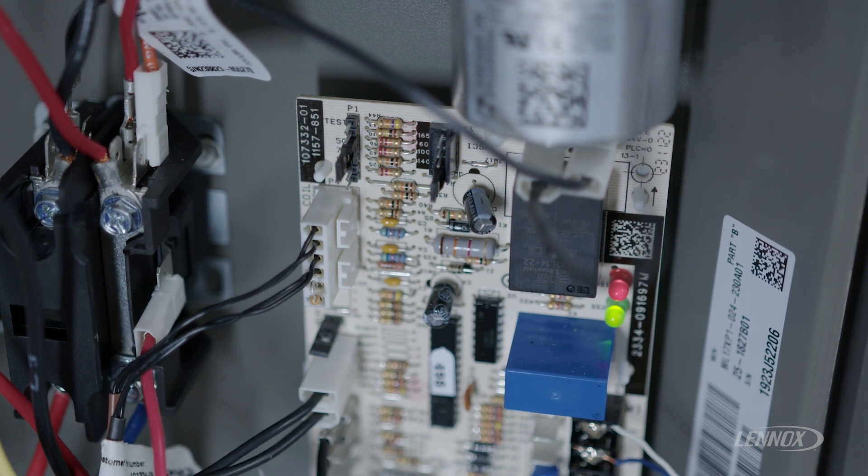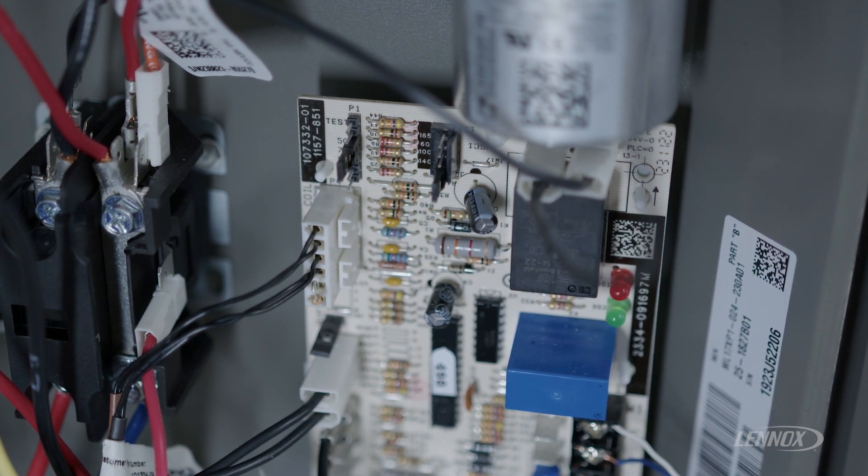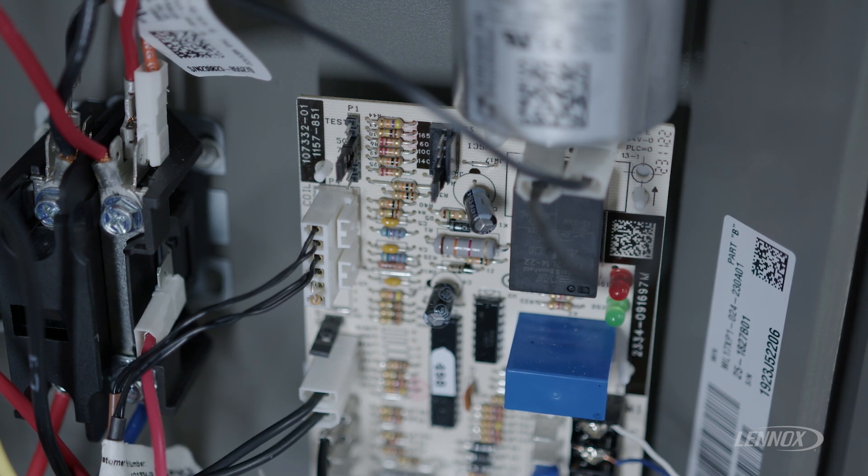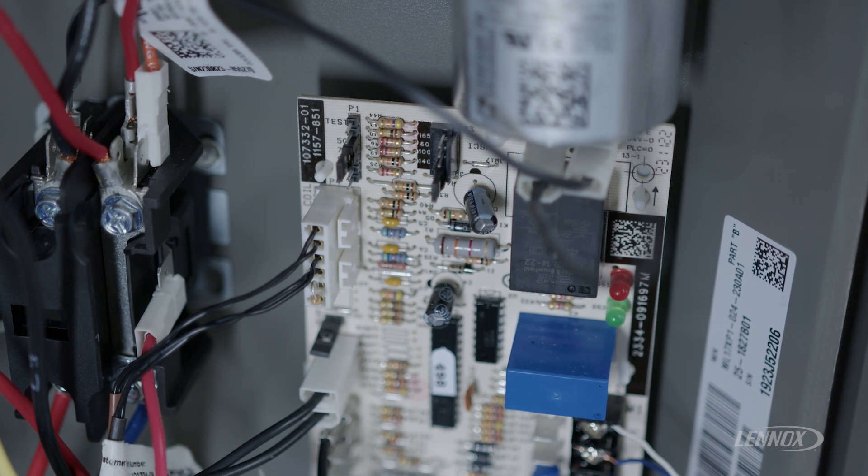And when you know you're in defrost, the compressor will be running. The condenser fan motor will not be running. And this cycle will run for a minimum of 14 minutes or until the defrost thermostat gets to its set defrost termination set point.